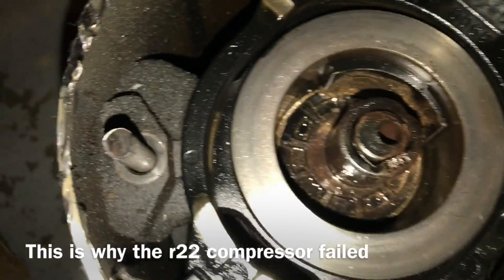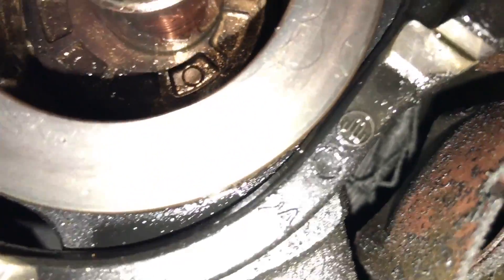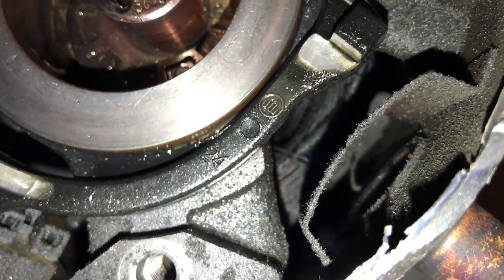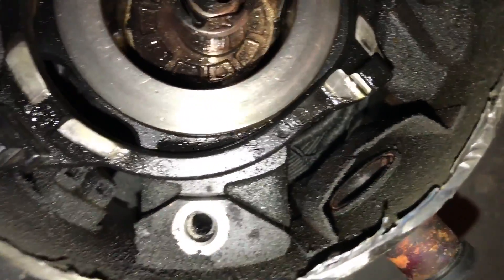It's got a lot of copper plating on there. It wore out the bearing — it's got a lot of play in it. But this is where the compressor grounded out. See that wire right there? It came off that bundle. It's touching right underneath the suction inlet — right there. It's actually gone on the bottom. That's when something gets grounded: the wires will actually touch the surface of the compressor.